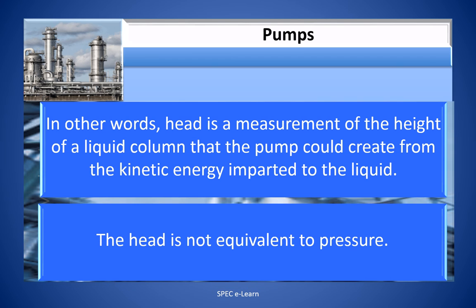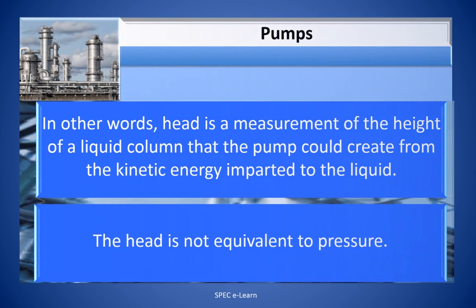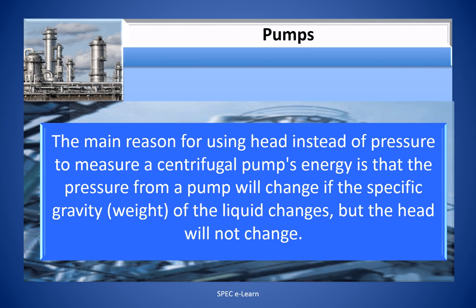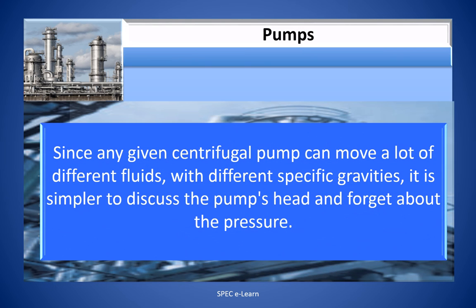The head is not equal to pressure. The main reason for using head instead of pressure to measure a centrifugal pump's energy is that the pressure from a pump will change if the specific gravity of the liquid changes. Since any given centrifugal pump can move many different fluids with different specific gravities, it is simpler to discuss the pump's head and forget about the pressure.